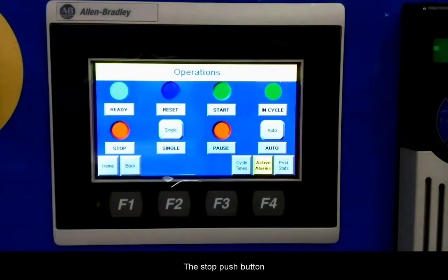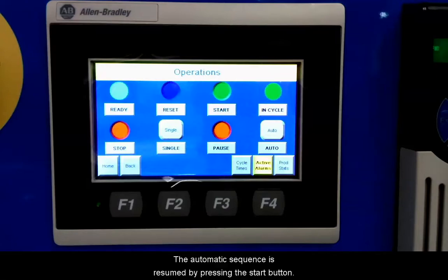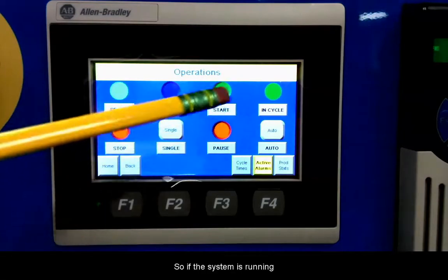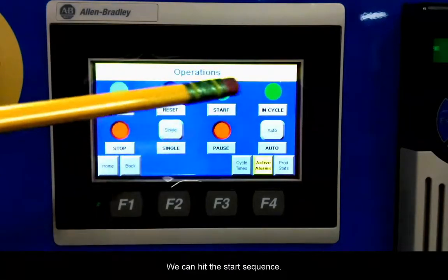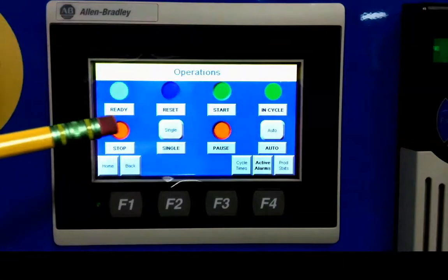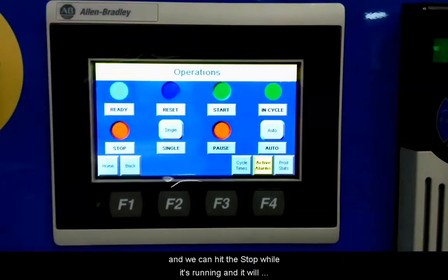The stop push button, when this button is pressed while in automatic mode, the system will complete all steps of its current sequence and halt. This is a cycle stop function. The automatic sequence is resumed by pressing the start button. So if the system's running, we can hit the start sequence and we can hit the stop while it's running, and it'll complete the cycle and we will halt its operation.